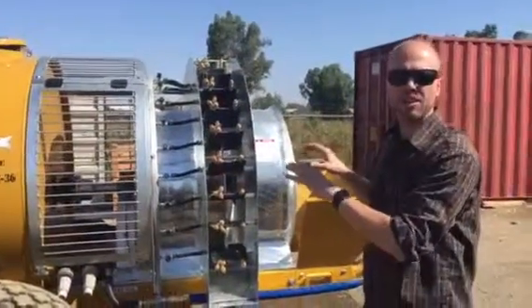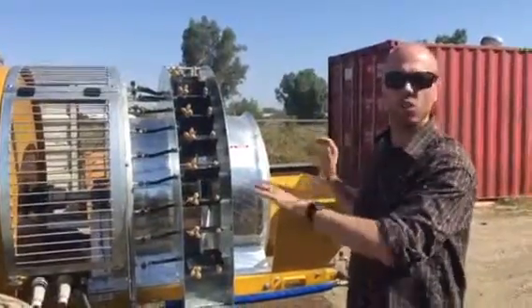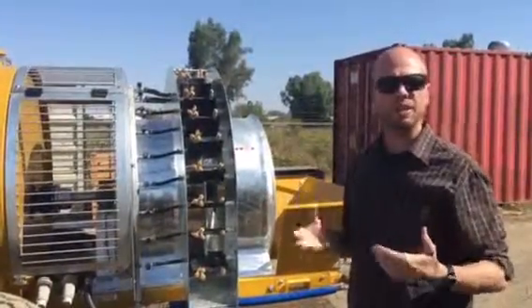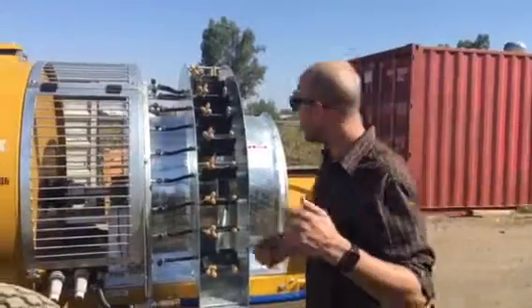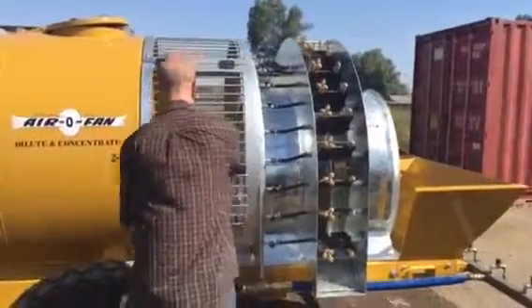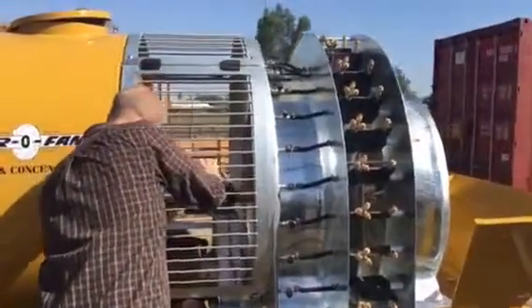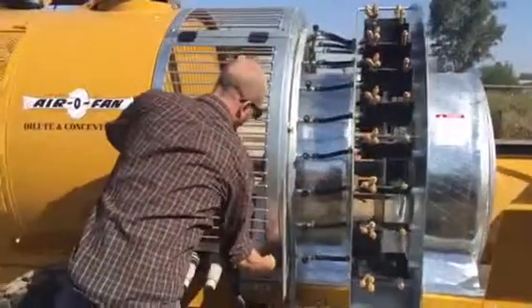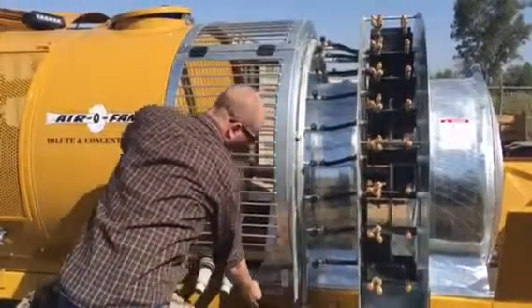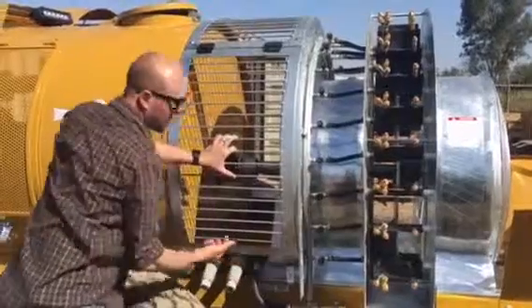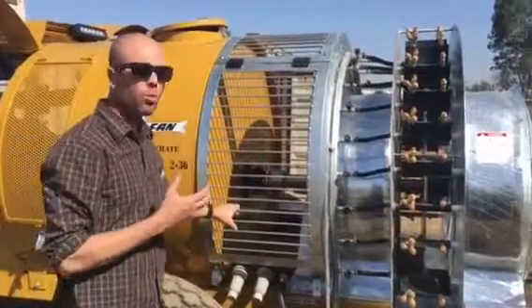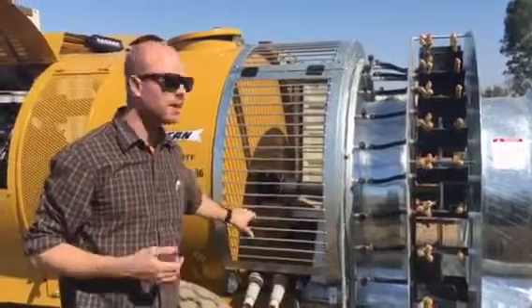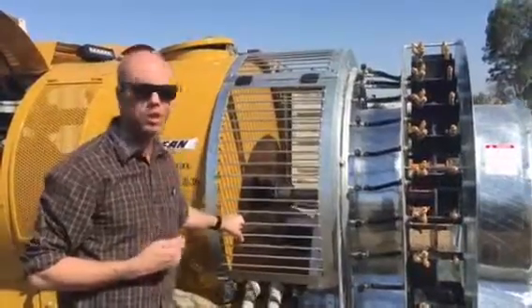Fan shaft bearings. So this is the most critical part on this whole piece of equipment. You want to grease those bearings until they actually purge grease. So if you take a look at the bearings on this unit, this is a Type E pillow block bearing. We do put grease points that access out to the outside without having to lift the guards. You never want to grease this machine while it's running. You never want to open these guards while it's running.